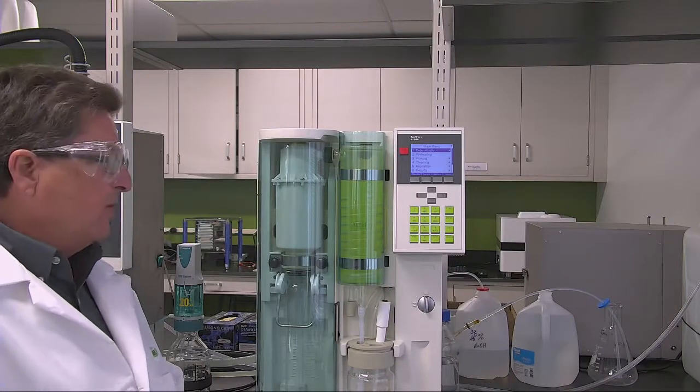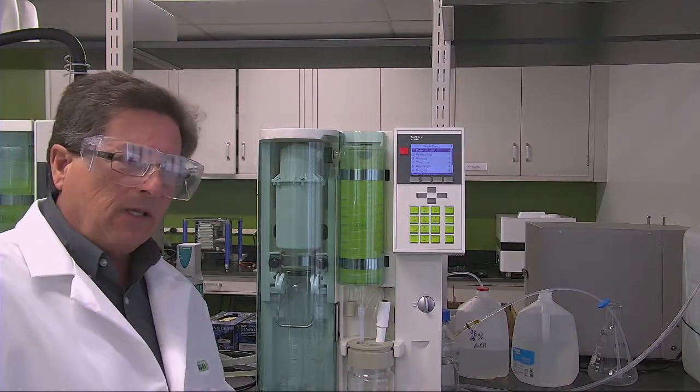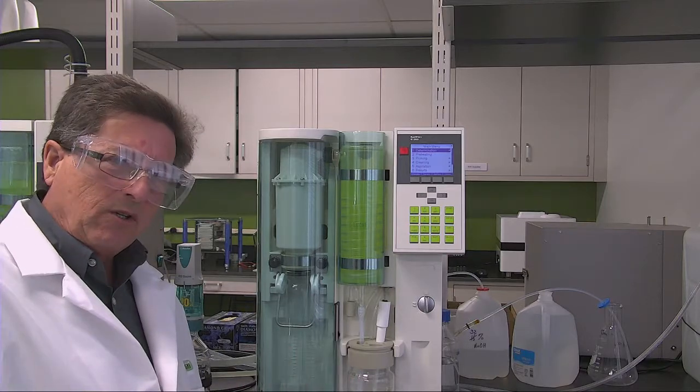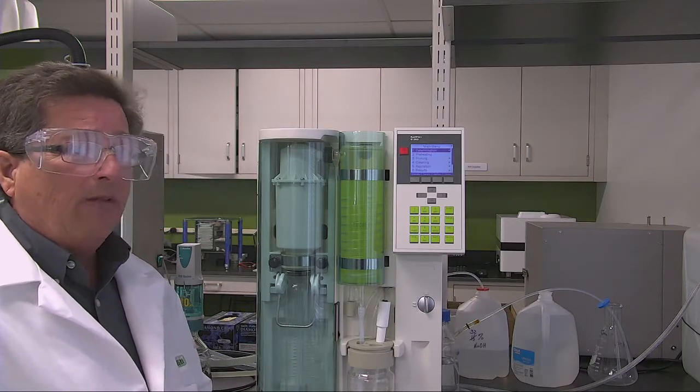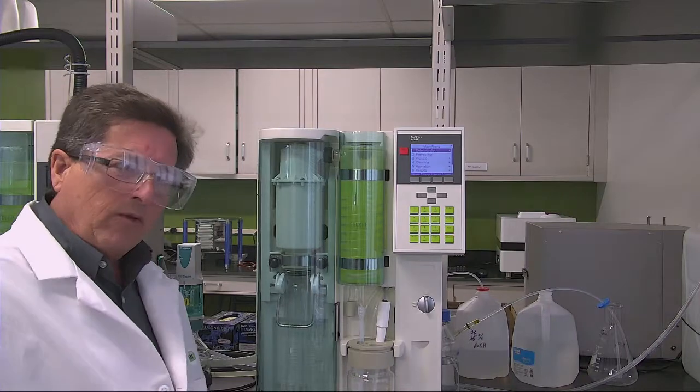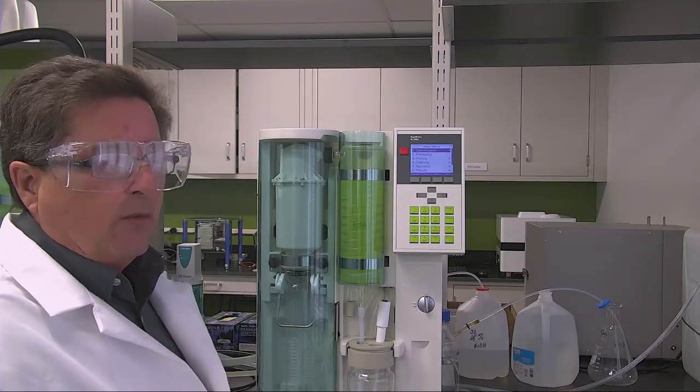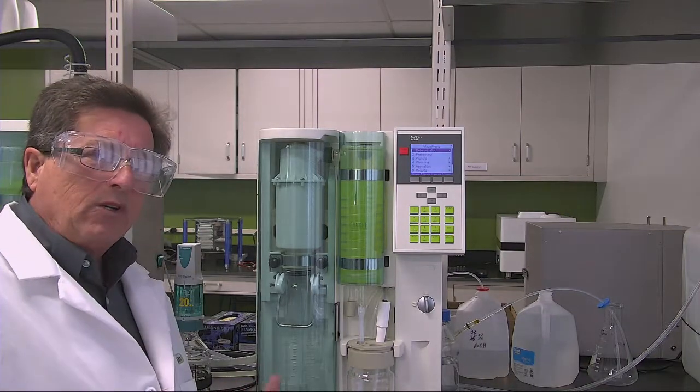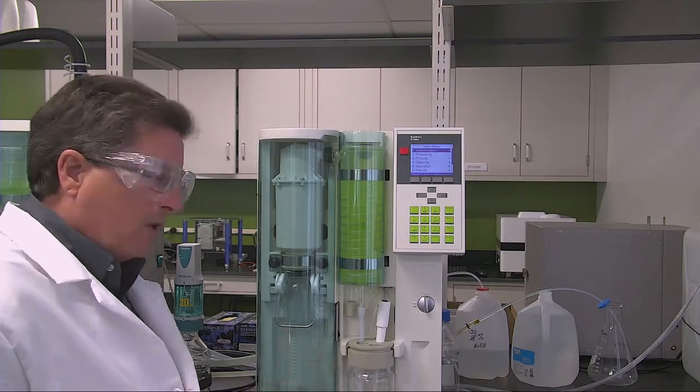One of the common problems we find is a leak. If you have aspiration issues or low nitrogen, you may have a leak in your system. Let's see how we can address the leaks on the front of the K360.